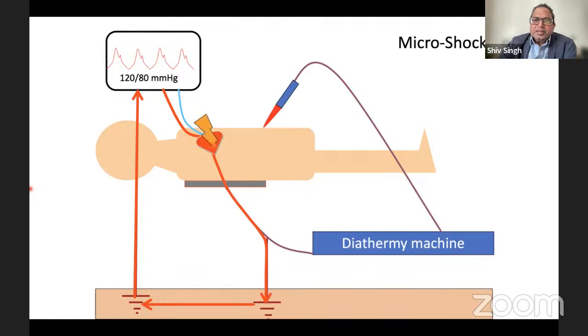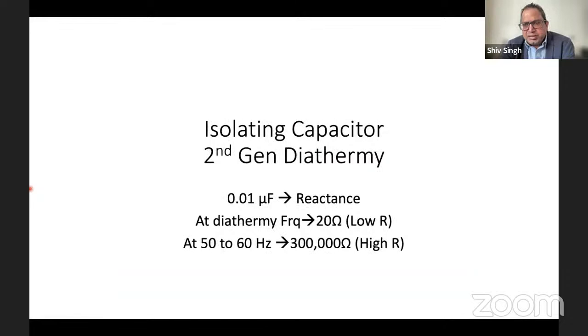So the second generation diathermy machines used something called an isolation capacitor. This was 0.01 microfarad, and its reactance was a very high resistance at the normal frequency. At 50 to 60 hertz, the normal frequency at which electricity is provided, the resistance is very, very high, so you could prevent microshock. But at diathermy frequency, in megahertz, the resistance is very low, so current can flow through it and you can complete the circuit through that.